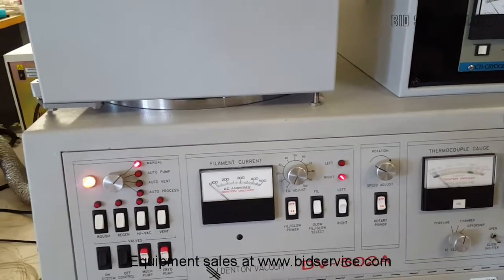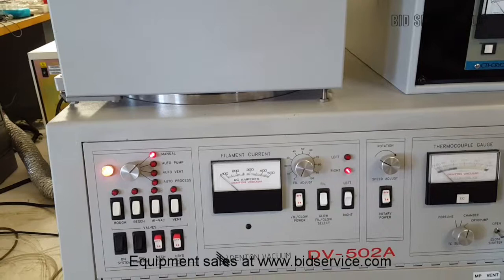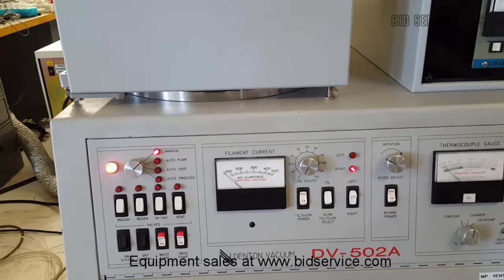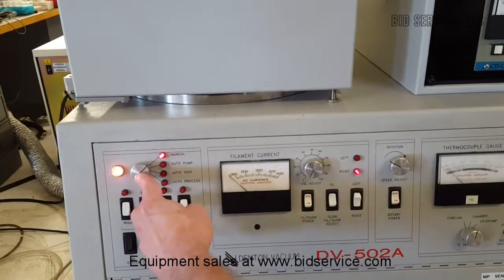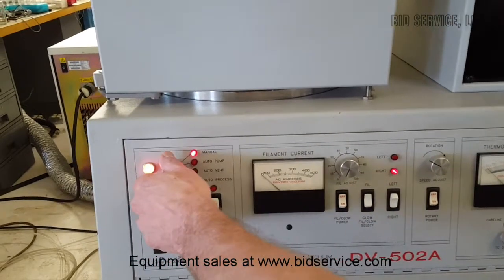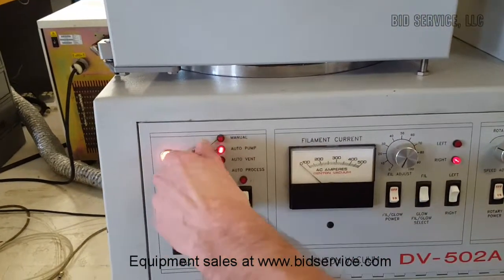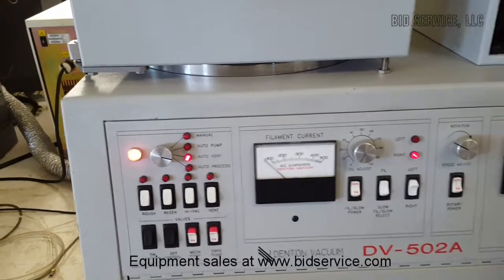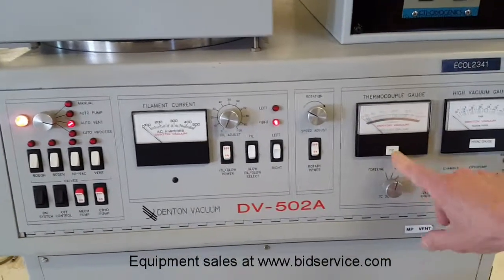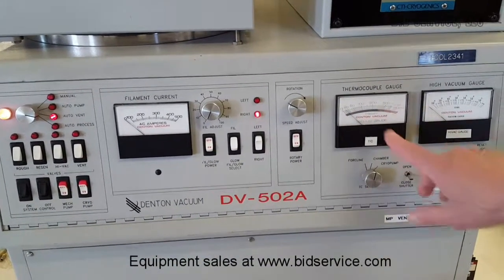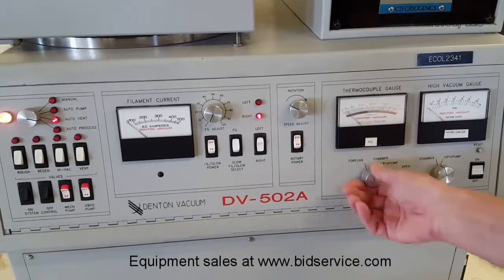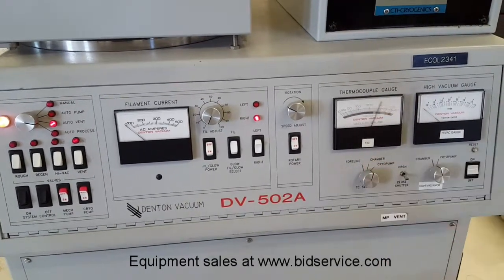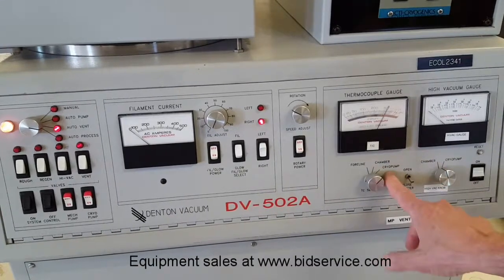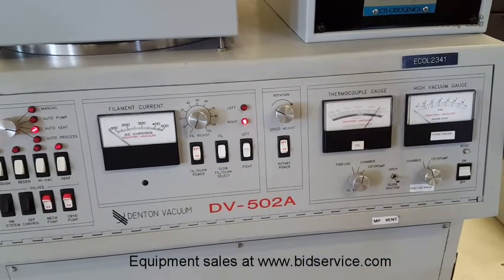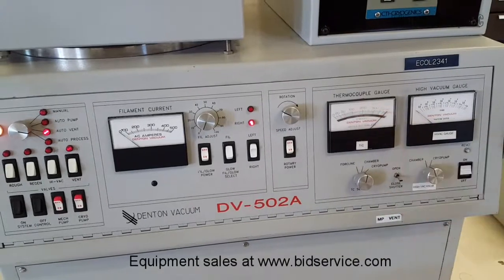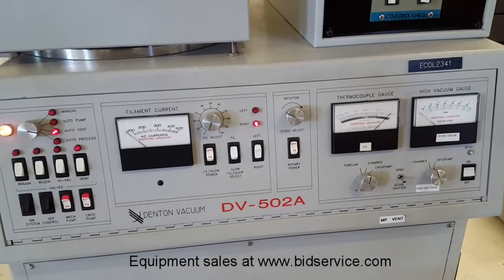What we'll do now is just show that the machine is operational. So what we can do here is go right into an auto process mode. Well, let's vent it first. So let's go to auto vent. Over here we have some TCs, a thermocouple gauge, and it's going to show you the pressure of the chamber. You can look at the foreline and the cryo pump when you're doing a regeneration. That's important. Well, let's go ahead and look at the chamber. You can see it's coming back up to atmosphere. Again, I'm only venting it with air.